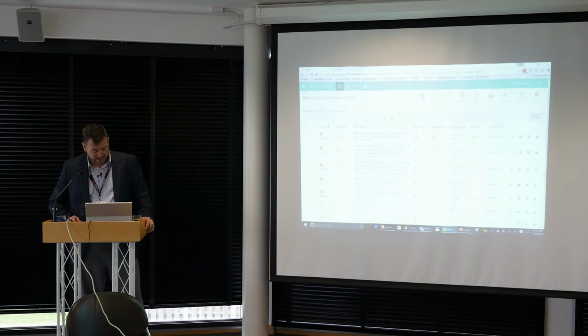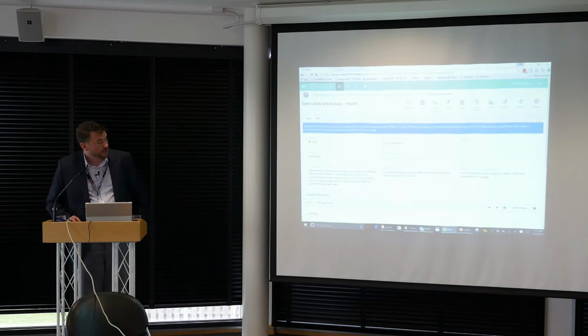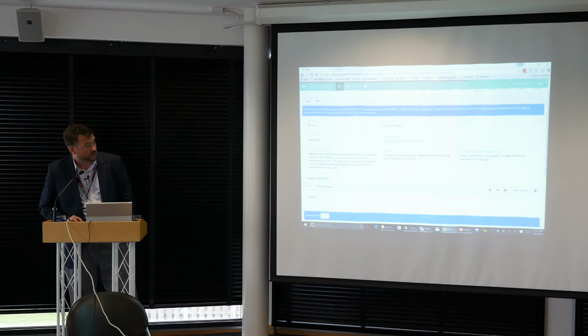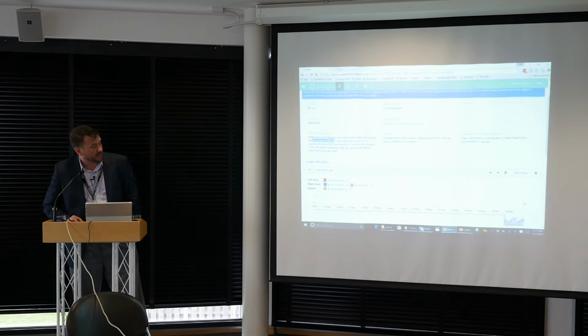So let's go look and see a couple of default protection diagnostics. So the heating coil is leaking, adding heat to the air while the valve is supposed to be closed. Let's look at that. So on my air handler, it's determined this based on the National Institute of Standards and Technology, NIST APAR rules. So somebody out in the industry, they've got industry standard rules for when things are wrong. It's telling me that my supply air temperature is more than 2 degrees above the mixed air temperature when the heating coil valve is closed during occupied hours.